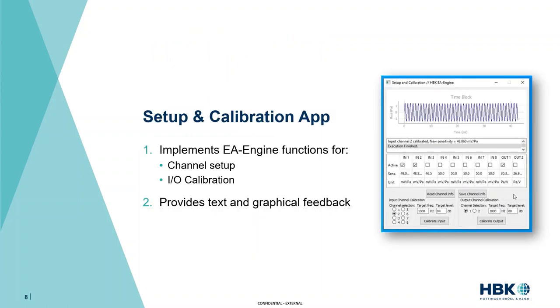The first app is the Setup and Calibration app, which implements a channel setup table along with input and output calibration functions. This allows you to activate and deactivate channels, manually update their sensitivity, and run input and output calibration so that channel sensitivity is automatically updated. It also implements graphical and text feedback so the user can follow what's going on with the EA Engine behind the scenes.